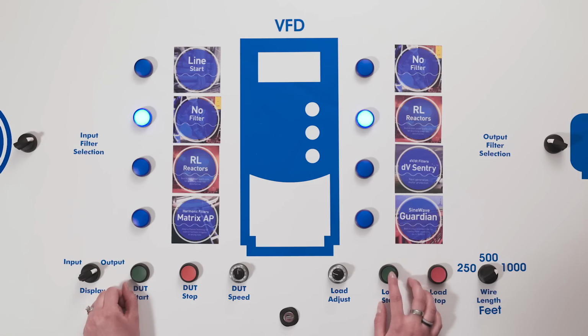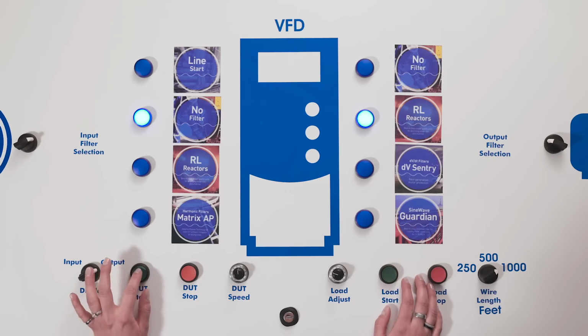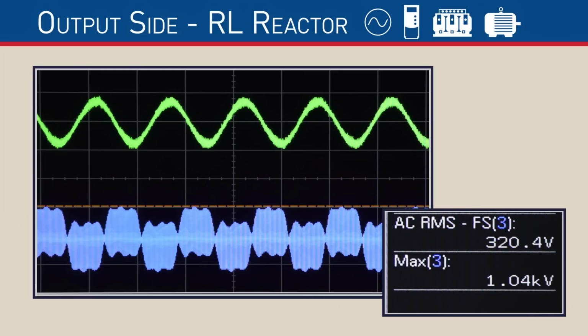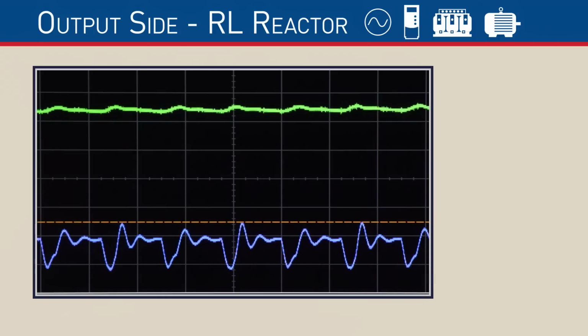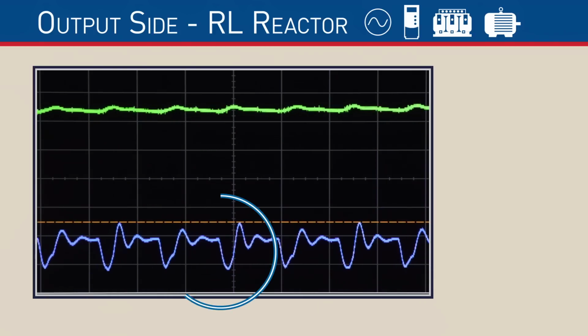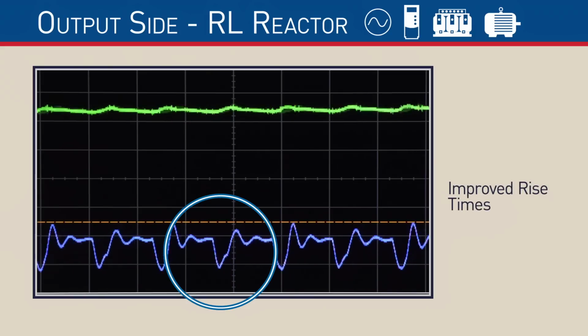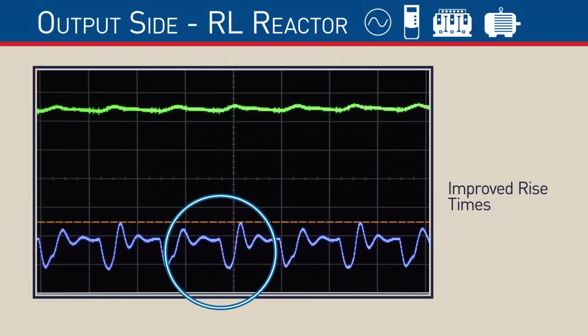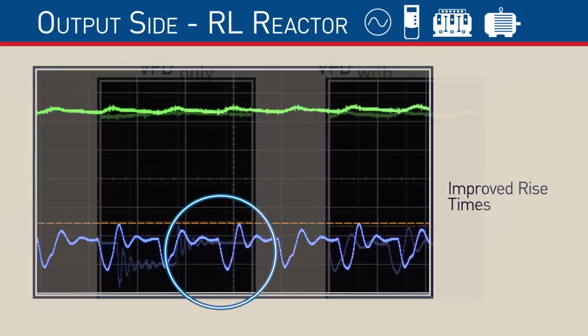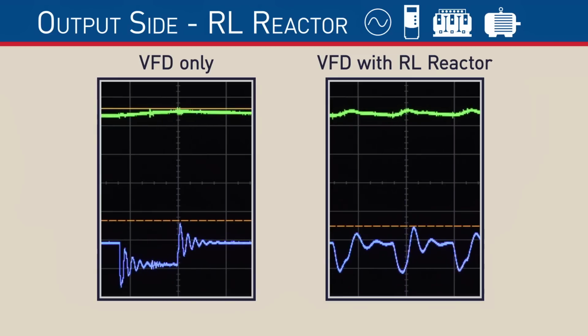With the RL reactor now connected, we can see a dramatically different wave shape. We have brought the peak voltage down considerably from 1400 volts to 1000 volts. And as we zoom in, we see that the rise times have also improved. Both of these reduce the stress on the motor's winding insulation and ultimately extend the motor's life.